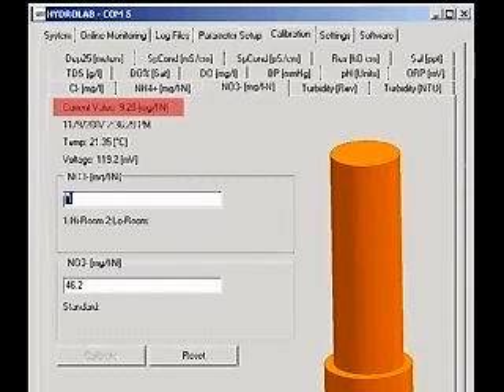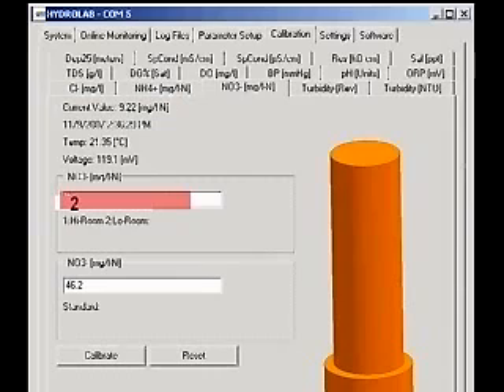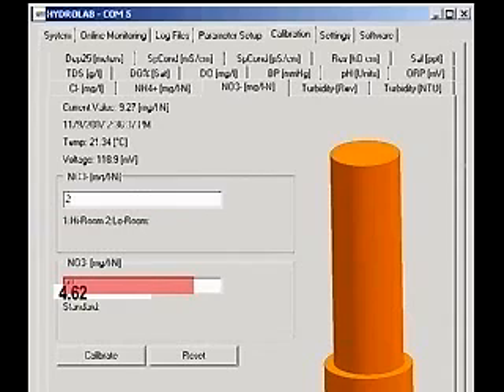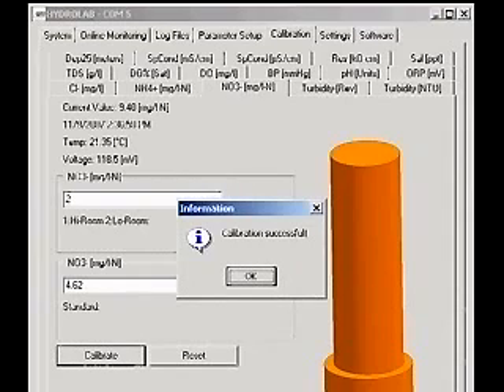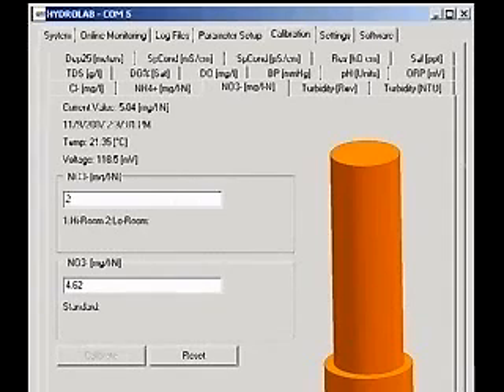When the readings are stable, type a value of 2 in the first box to designate the low standard. Type 4.62 into the second box and click Calibrate. A calibration successful message will appear. Record the temperature.